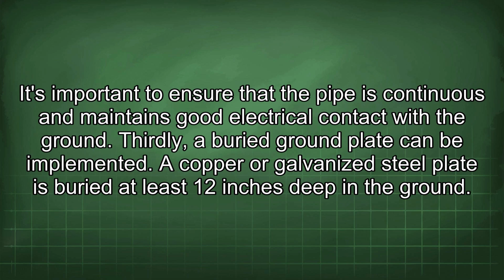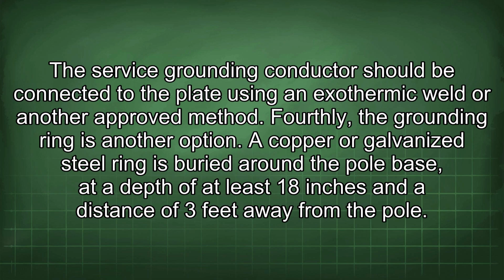Thirdly, a buried ground plate can be implemented. A copper or galvanized steel plate is buried at least 12 inches deep in the ground. The service grounding conductor should be connected to the plate using an exothermic weld or another approved method.